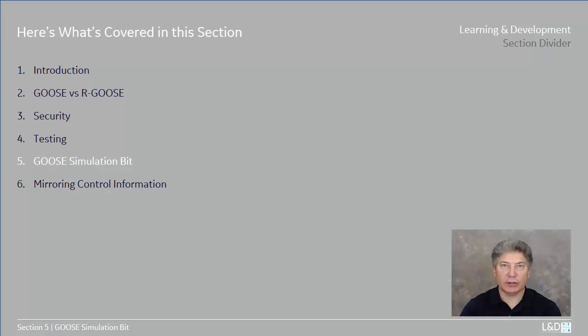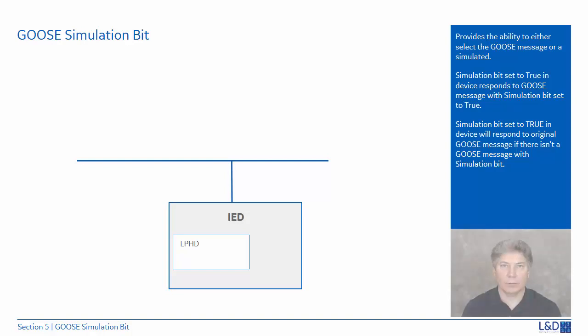In this section, we'll take a look at the GOOSE simulation bit and how it impacts testing. IEC 61850 Edition 2 cleared the confusion associated with testing the IED. Edition 2 added the feature where the device can subscribe to the GOOSE message either from the real source or from a simulator. With the advancements in test equipment, they have the ability to generate simulated GOOSE messages.